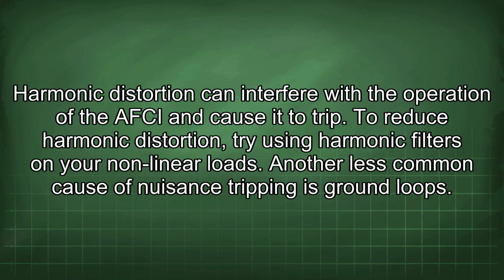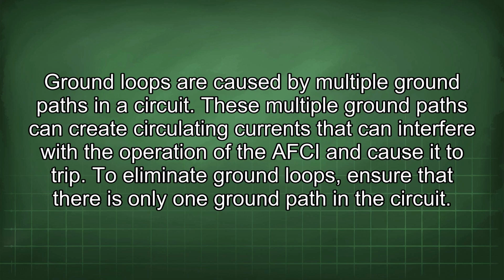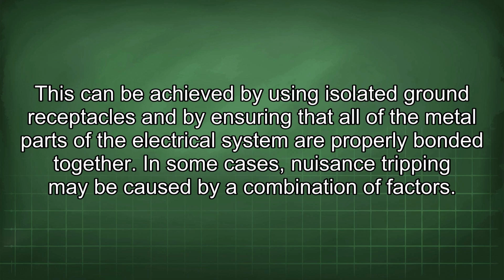Another less common cause of nuisance tripping is ground loops. Ground loops are caused by multiple ground paths in a circuit. These multiple ground paths can create circulating currents that can interfere with the operation of the AFCI and cause it to trip. To eliminate ground loops, ensure that there is only one ground path in the circuit. This can be achieved by using isolated ground receptacles and by ensuring that all of the metal parts of the electrical system are properly bonded together.